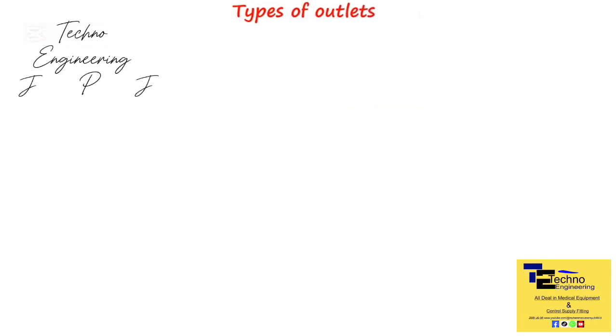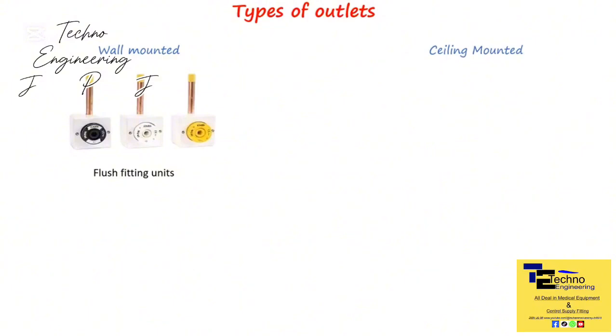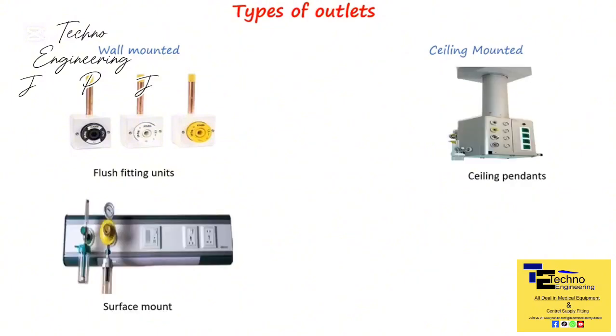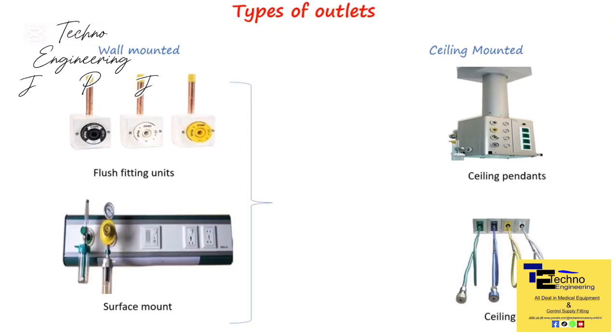Terminal unit outlets can be mounted on either the wall or the ceiling. There are various types of installations for terminal gas outlets available, such as flush fitting units, surface fitting units, ceiling pendants, and hoses, depending on the facility's requirements. Flush units and surface mounts are commonly found on bed heads in wards and ICUs, while pendants and ceiling hoses are typically utilized in operating theaters.